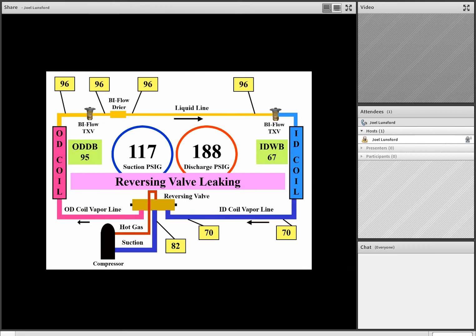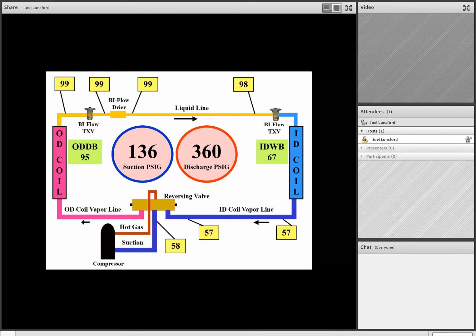In this service call here, it's an R410A system. We're in the cooling mode of operation. We have 136 pounds of suction pressure. At 136 pounds of suction pressure for a 410A unit, we see that we've got a pressure temperature conversion of about 47 degrees. Excuse me. And our temperature on the vapor line leaving the cold coil is 57. So in this example, our superheat is about normal.